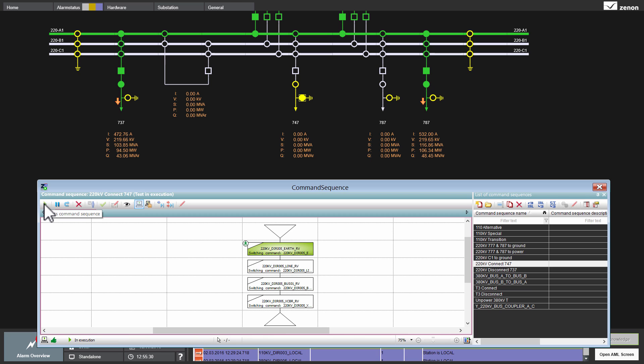First, the earthing switch is opened. Then, the line disconnector would close. The busbar disconnector would close and finally the circuit breaker.